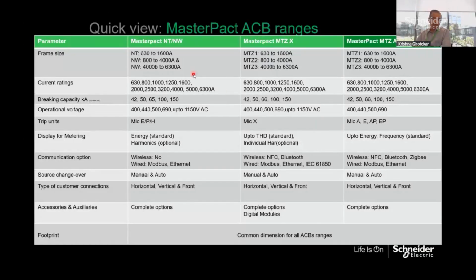A quick comparison outlook. You have NT NW, you have MicroLogic X of MTZ, and MicroLogic Active. I will just point out the differences. Current rating wise, performance, as I mentioned, is the same. Only the 65 kA in NW has become 66 kA, whether it's with MicroLogic X or MicroLogic Active. Here you start with the E-type trip unit, and then you have P and H as the high-end trip units, which have energy as a standard. If you go with the high-end trip unit H, which has very high features, it comes with harmonics. In X, you have up to THD, total harmonic distortion, and if you need individual odd order and even order harmonics, you can add on the software. Whereas for Active, it can be either A, which is energy, or E, and frequency is standard for the E-type trip unit.